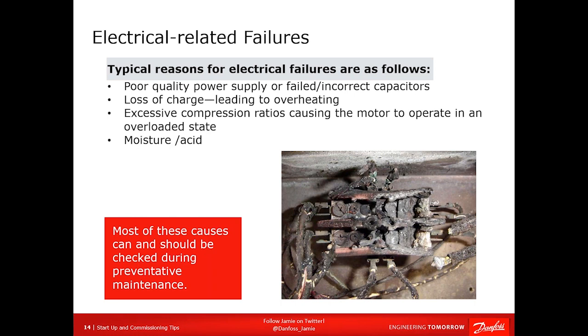So poor quality power. Expect to see this during periods of high air conditioning load, brownout conditions, but also expect them in places like marinas and resorts that are far off the grid. They don't have high transmission lines running direct to them, and you can get an issue where your voltage is 10% lower than it should be. And this generally happens during summertime when everybody else is using power.